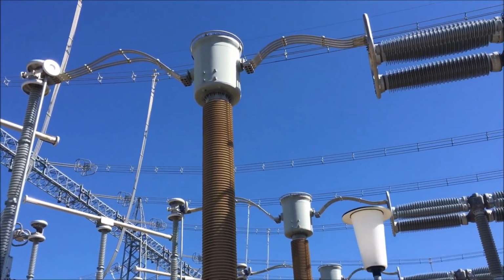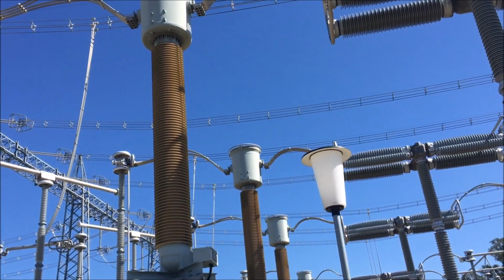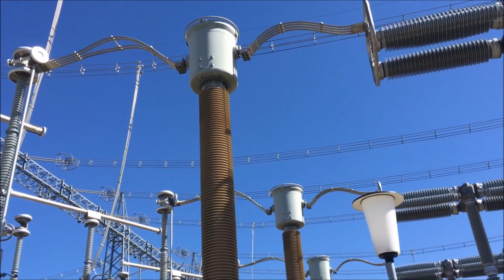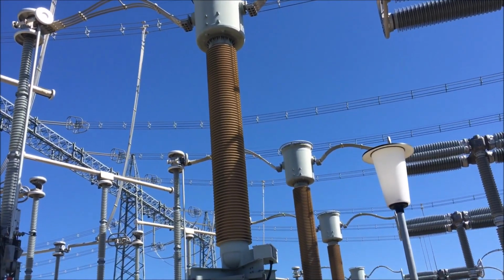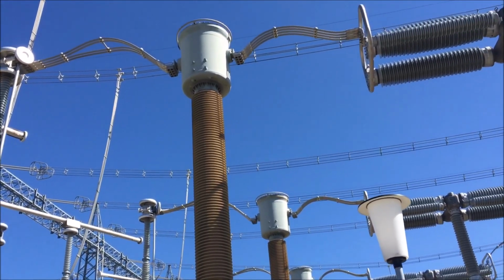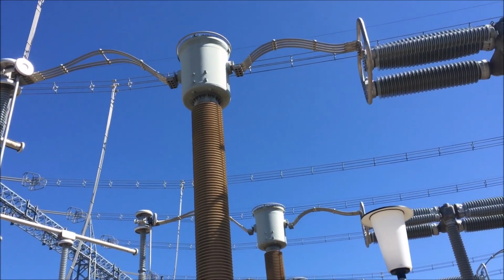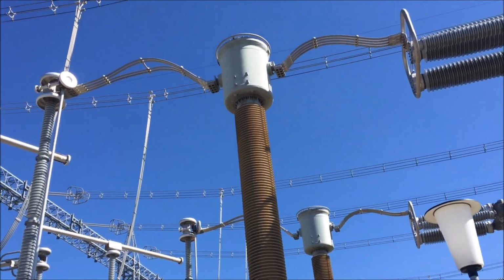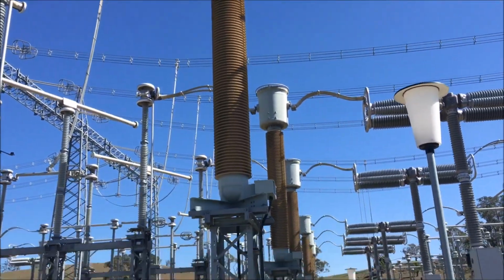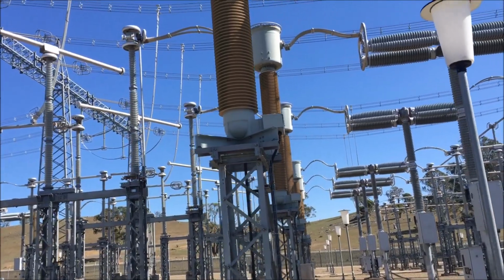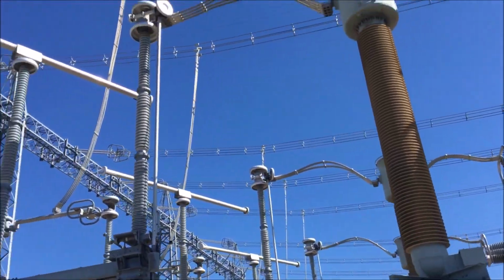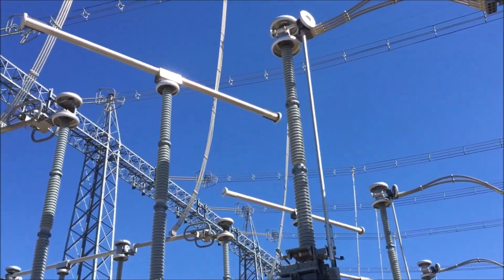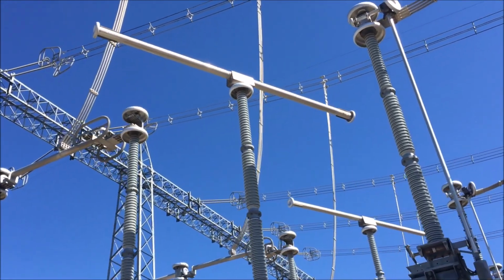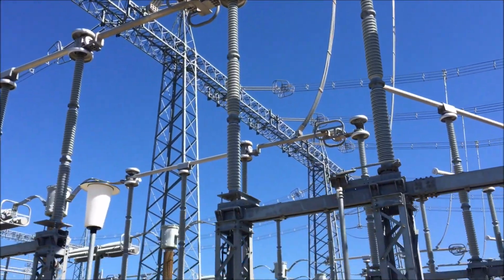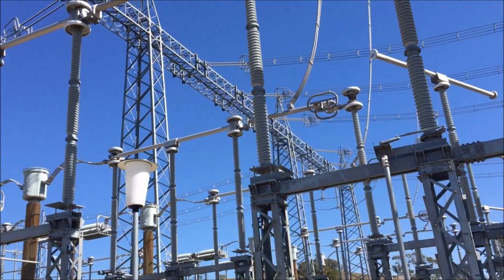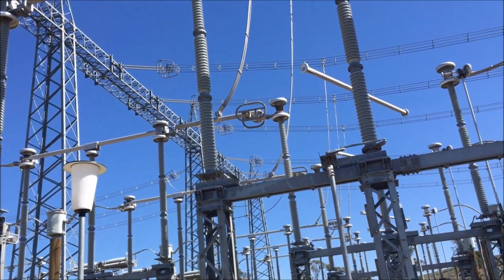Then we come to the current transformers, much like the VT, except these convert the current down to a usable quantity. These are 3,000 to 1 ratio, so if there's 3,000 amps up the top, we'll get 1 amp down the bottom, which we can send into the relays. Big earth switch, isolator's open because we've got one of the trannies out today. And we're going to have a look at the trannies. They're pretty big.